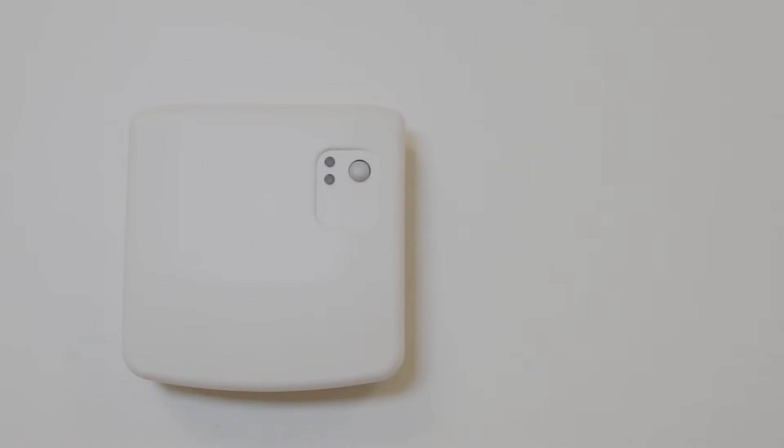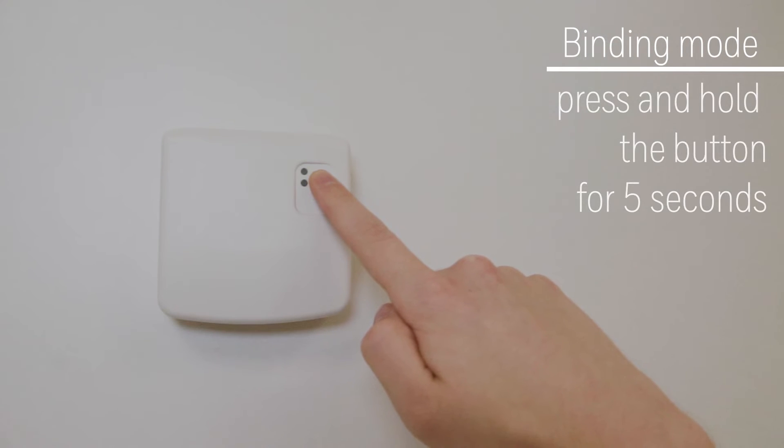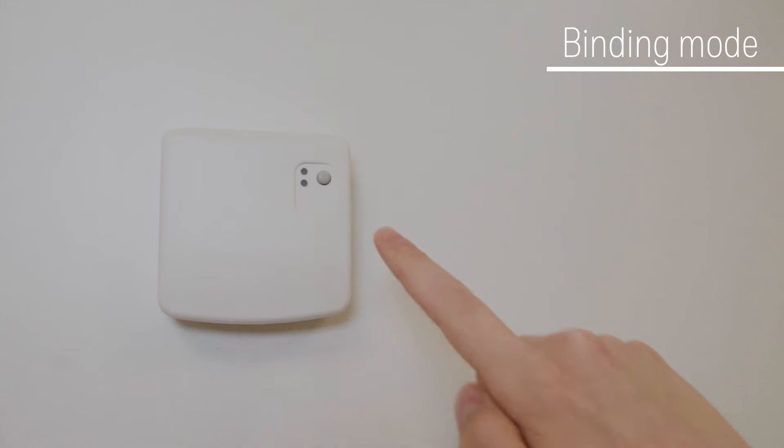The BDR-91 relay box has a single red and a single green LED indicator. Binding. The binding mode is activated by pressing and holding a button for 5 seconds. During binding mode, the relay will be set to the off condition. Red light will flash on and off every second while in binding mode. Successful binding will turn the red light off.